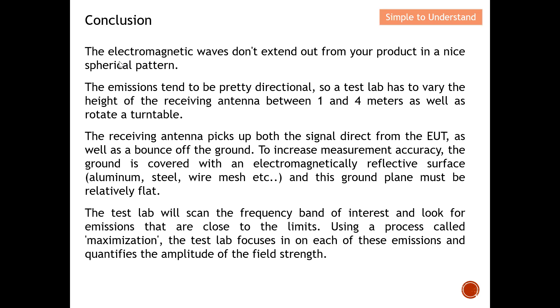In conclusion: electromagnetic waves don't extend out from your product in a nice spherical or cone-shaped pattern. The emission tends to be quite directional. Therefore, the test procedure must vary the height of the receiving antenna between 1 and 4 meters and rotate the turntable, because radiation is directive and will pinpoint a certain direction. The receiving antenna picks up both the direct signal from your EUT and the signal bounced off the ground.